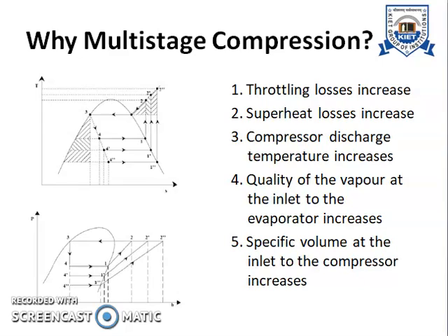So let us take the temperature requirement now as minus 60 degrees Celsius or minus 50 degrees Celsius. Now the throttling loss increases, as represented by the triangle area as discussed in the previous case, plus the trapezoidal area, the middle one, shaded part. Okay. So this is how the throttling loss increases as we move to a lower evaporator temperature.